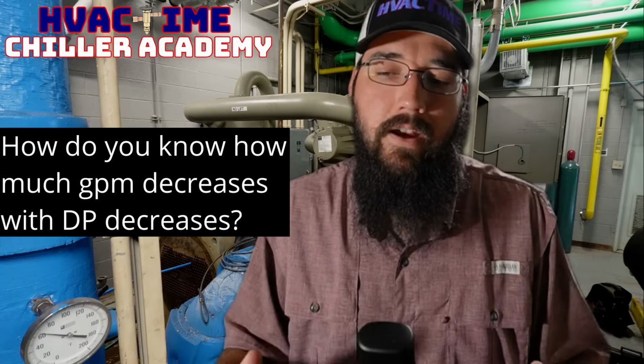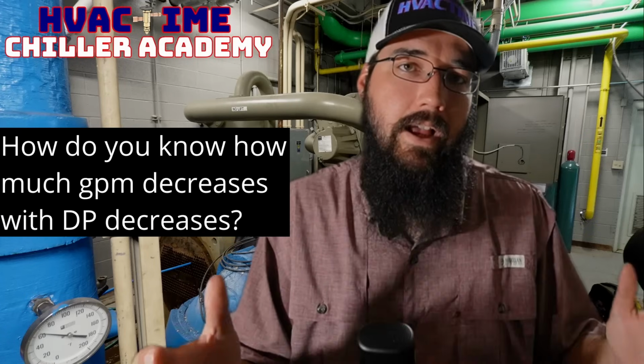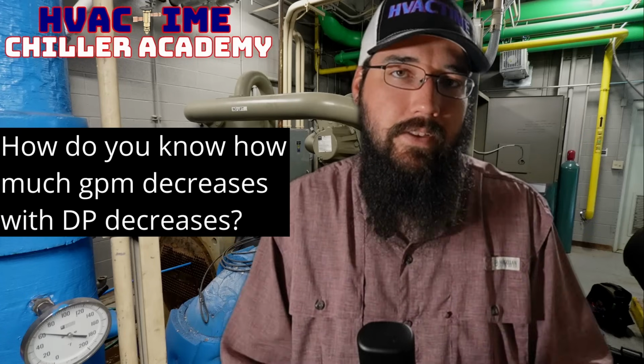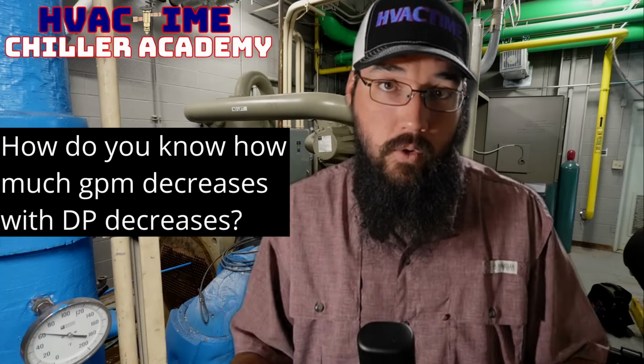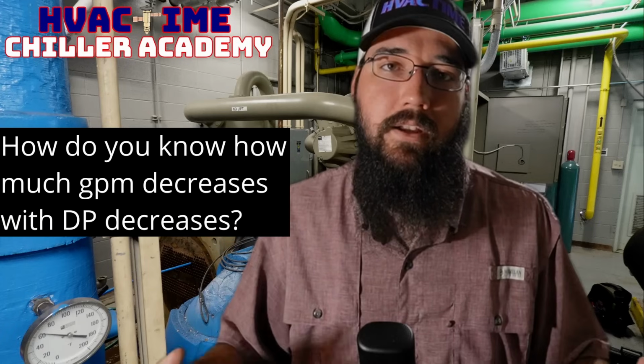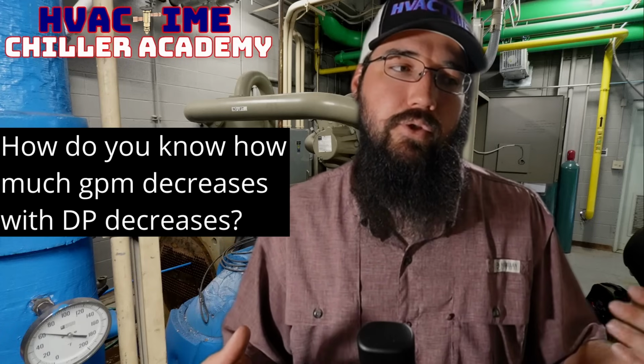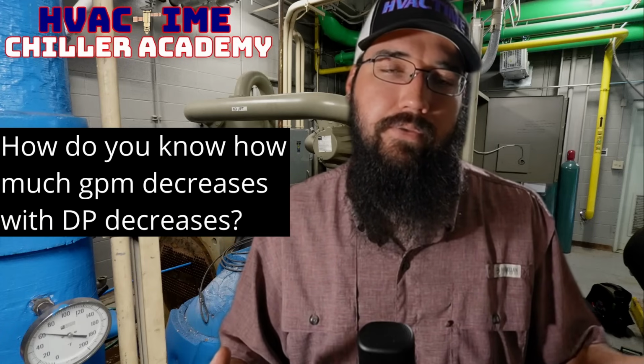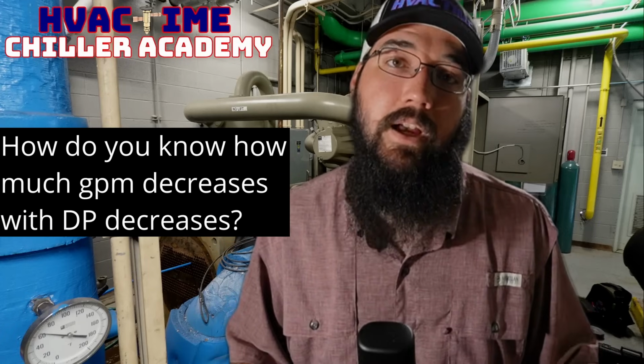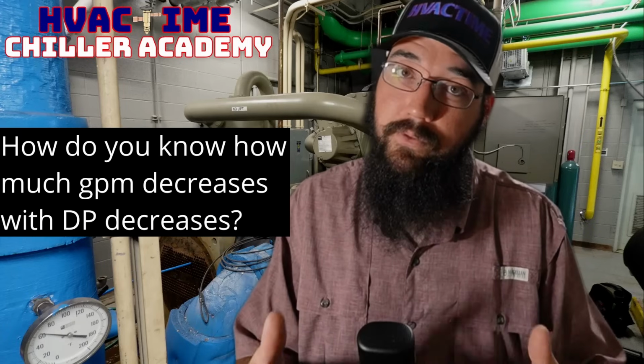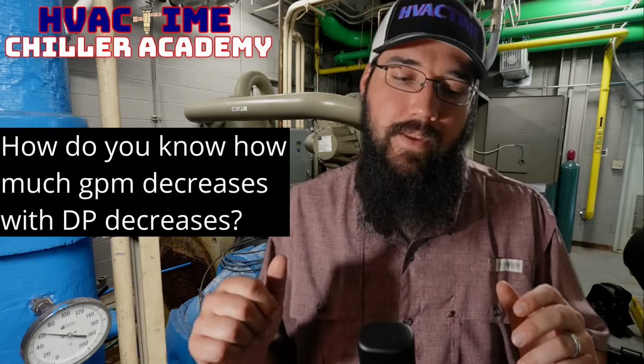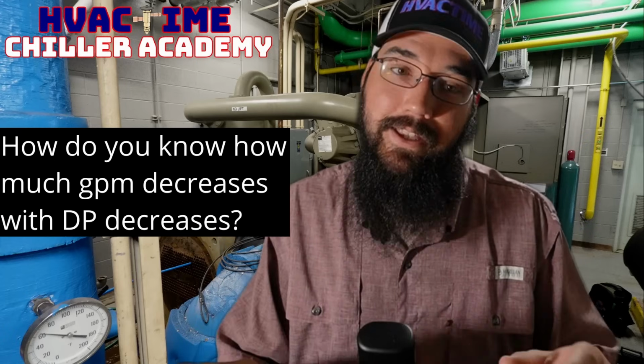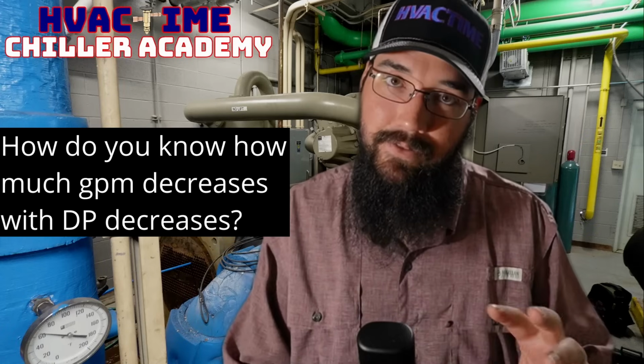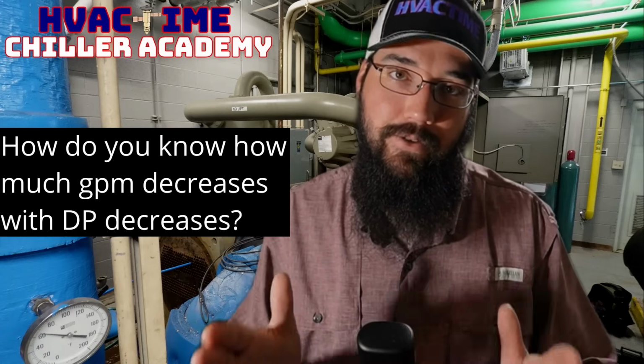If you don't have the submittal data and you don't have the charts you need—that basic information, which is not always publicly available—unless you've got a flow sensor or flow meter of some kind that you can trust. And that's the other issue with flow meters: they've got to be calibrated correctly, they've got to be installed correctly. There's a lot of technicality into using a flow meter the right way.